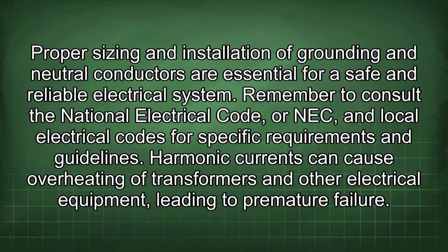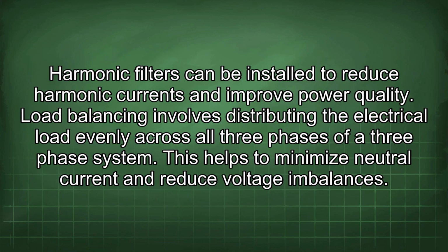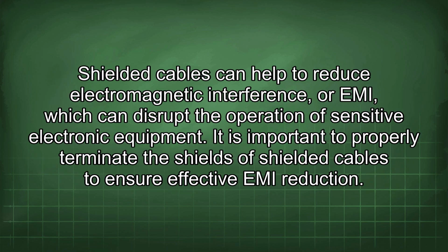Harmonic currents can cause overheating of transformers and other electrical equipment, leading to premature failure. Harmonic filters can be installed to reduce harmonic currents and improve power quality. Load balancing involves distributing the electrical load evenly across all 3 phases of a 3-phase system. This helps to minimize neutral current and reduce voltage imbalances. Shielded cables can help to reduce electromagnetic interference, or EMI, which can disrupt the operation of sensitive electronic equipment. It is important to properly terminate the shields of shielded cables to ensure effective EMI reduction.